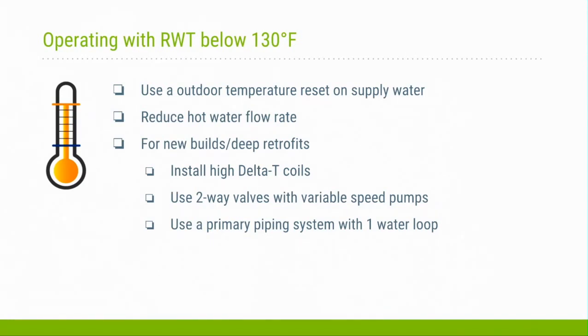Another is using two-way valves with variable speed pumps. What this does is reduce mixing. With a three-way valve, you divert some water through the coil as needed, and then it mixes back in with the main loop. And every time you do that remixing, you bring your return water temperature back up. If you have two-way valves, what you end up doing is constraining the valves, tightening them down, which gets back to that reduced hot water flow rate. But if you're going to go that way, you really need variable speed pumps. Otherwise, the pressure on the system is going to get too high. And then one last option is using a primary piping system with one water loop.